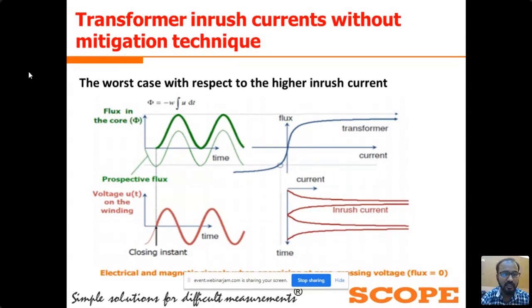Now we can see the worst case with the power transformer, which will cause the higher inrush current. In this waveform, at my cursor position, this is a voltage waveform and this is a magnetic flux. So if we close the power transformer near voltage 0, you can see at this moment the prospective flux at the power transformer core is at maximum value. If we open the power transformer at this moment, the prospective flux in the transformer core is near 1 pu.